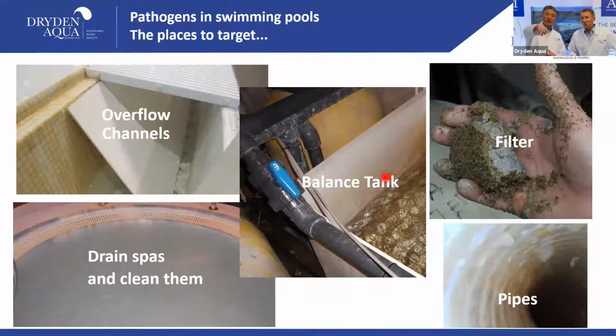Here also you see this biofilm on the balance tank. The balance tank has the most contaminated water, which is why you also have good growth of biofilms in these pipes. That's difficult to brush and clean. Difficult to brush if you have 2 inches. Most brushes are not long enough, and your arms are maybe not long enough, so you have to do this in a chemical way. But really, the key one, 95% of the problem is filter media.